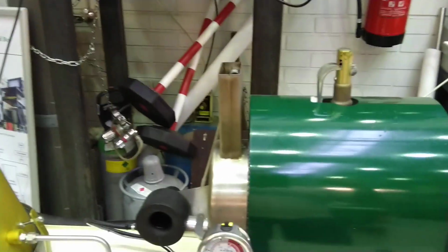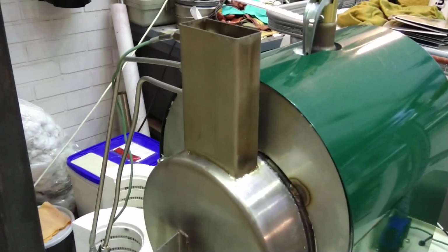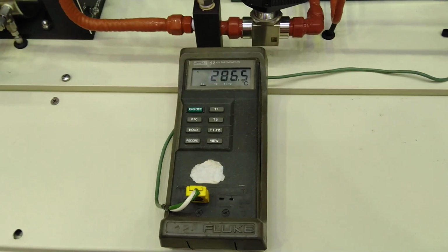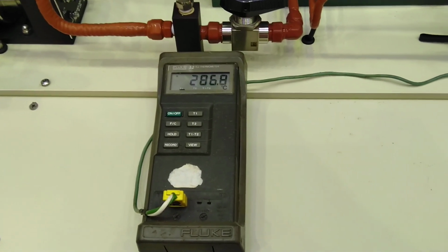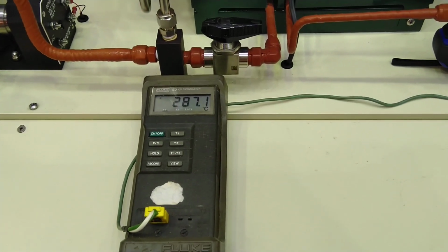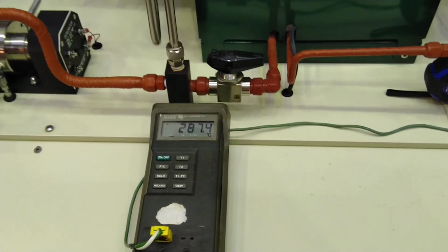Some of the measurements, as we showed in the other video, is for the gas analyzers. You will see they are connected, the two metal rods in the back. The third measurement is the green wire, which brings us to this reading, and is the temperature reading for the flue gas. So you can see now in the preheating phase, the temperature is rising with the buildup of temperature and pressure in the boiler.